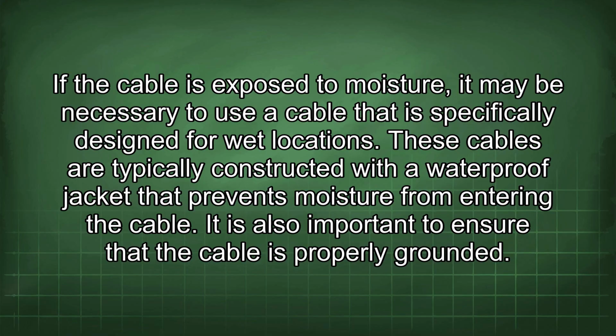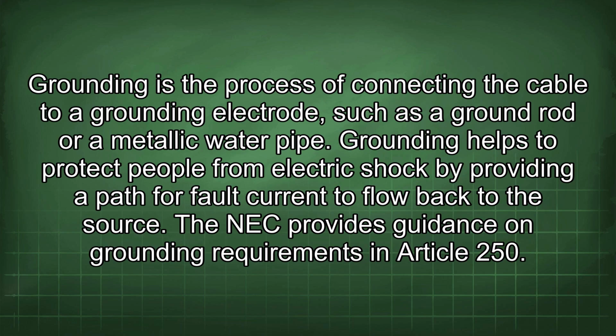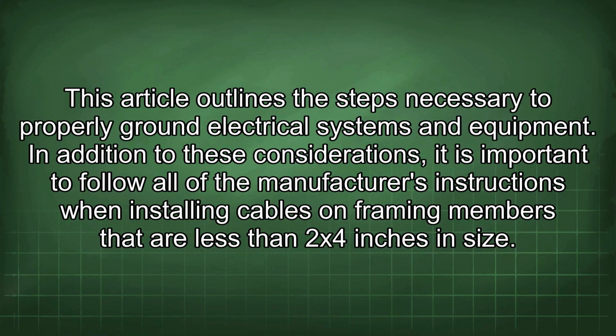It is also important to ensure that the cable is properly grounded. Grounding is the process of connecting the cable to a grounding electrode, such as a ground rod or a metallic water pipe. Grounding helps to protect people from electric shock by providing a path for fault current to flow back to the source. The NEC provides guidance on grounding requirements in Article 250. This article outlines the steps necessary to properly ground electrical systems and equipment.